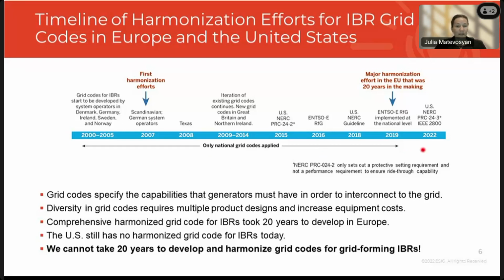So these grid codes specify capabilities for generators that they must follow to interconnect to the grid. Diversity of grid codes that we've seen historically requires multiple product designs and increased equipment costs. Comprehensive harmonized codes took 20 years to develop in Europe, and in the US, there is still no harmonized grid code that applies to existing conventional inverter-based resources today. So there is an IEEE 2800 standard that was approved in April last year, but it needs to be adopted to apply.